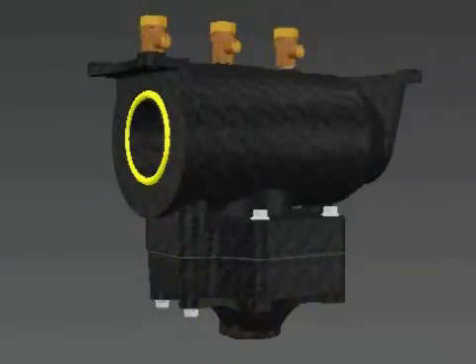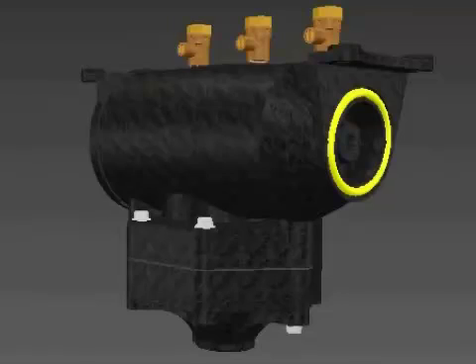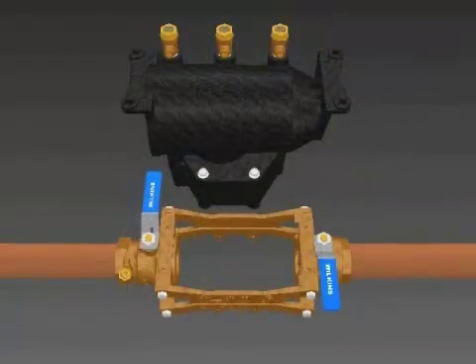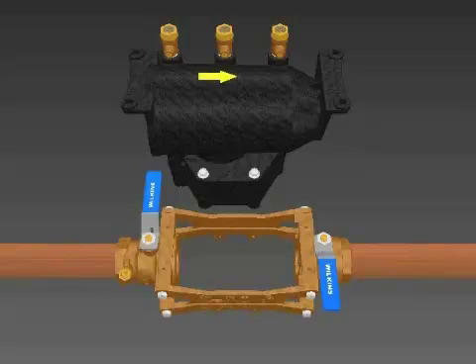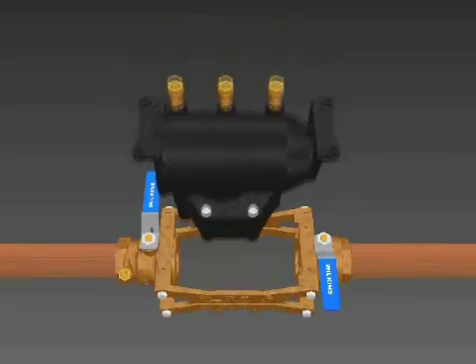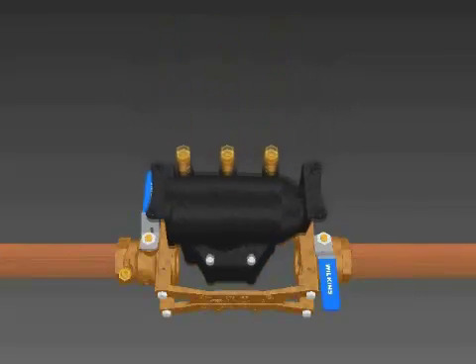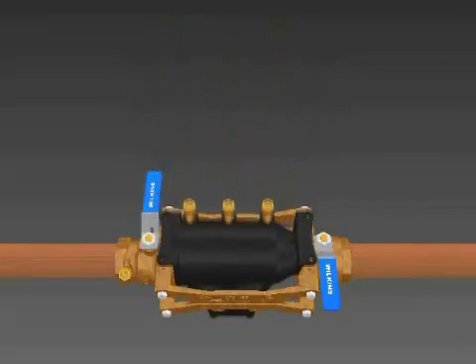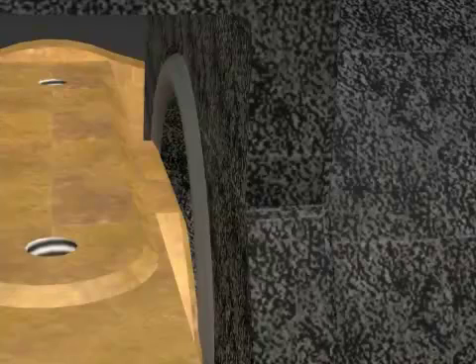Clean the O-rings at the ends of the housing and replace if necessary. Insert the two O-rings into the grooves in the housing. Lubricate the face of the housing O-rings. Make sure you have the housing facing the correct flow direction and place it down into the body. Push down with a rocking motion until the housing is flush against the bronze body. As you push down on the housing, be careful that the O-rings do not extrude out of their grooves or become pinched by the upper edge of the body.